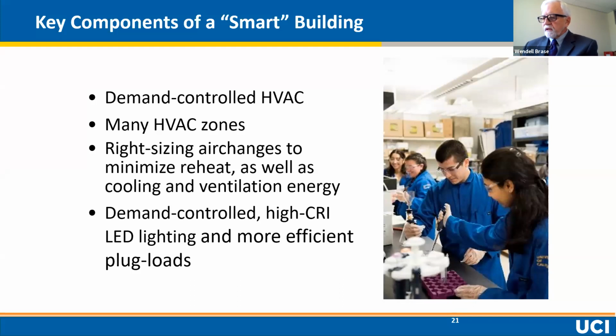If you want to call it smart, it needs to have demand-controlled HVAC. Demand-controlled could just be occupancy controlling HVAC, as well as lighting in a simple office building. But in a laboratory building, you'll see that we measure a lot of other things for demand control, like CO2, particulates, VOCs. This is all about precision control.